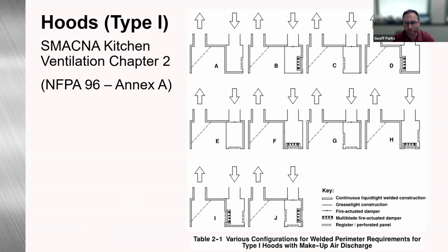Also in chapter 2, we have table 2-1. This is showing various configurations for the welded perimeter requirements of type 1 hoods with makeup air discharge. Essentially what these details are telling you, depending on how that makeup air discharge is tying into the hood, would tell you if a fire actuated damper or multi-blade fire actuated damper is required. So anytime that makeup is actually penetrating the continuous liquid tight welded construction, that's when you're going to have either a fire damper or multi-blade fire damper.